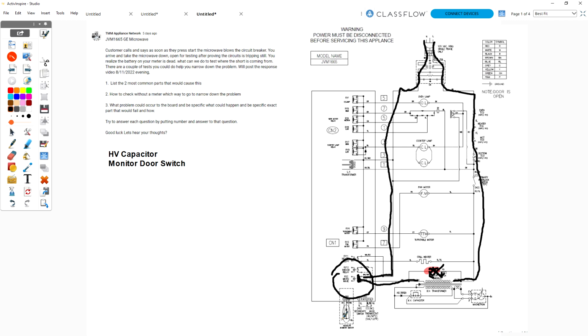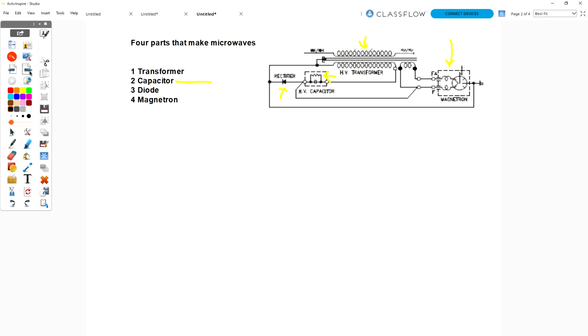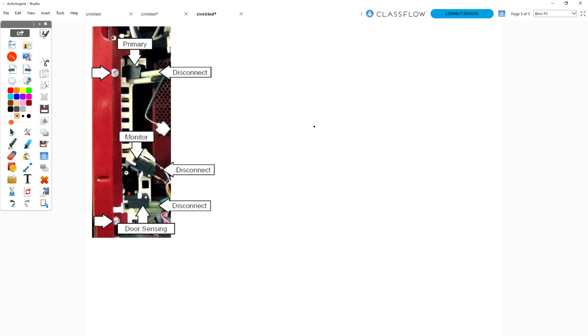Now, I got lucky. One time I was able to take the back end of my screwdriver and hit the relay on the board. And when I hit the relay on the board, it unstuck the contact, so to speak. But sometimes you have to replace both parts, and you need to check it before you leave that that part didn't fail.